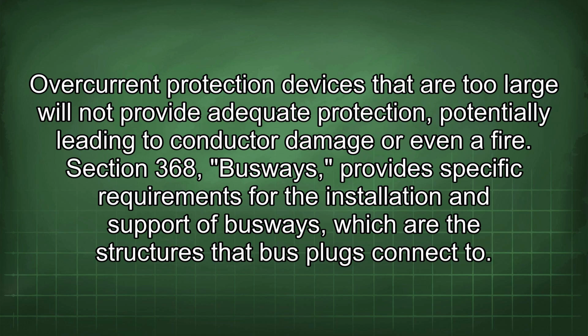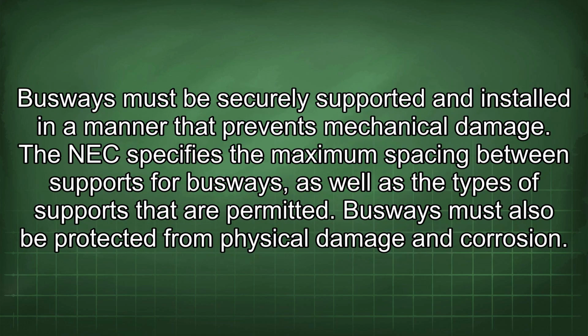Section 368 Busways provides specific requirements for the installation and support of busways, which are the structures that bus plugs connect to. Busways must be securely supported and installed in a manner that prevents mechanical damage. The NEC specifies the maximum spacing between supports for busways, as well as the types of supports that are permitted. Busways must also be protected from physical damage and corrosion.